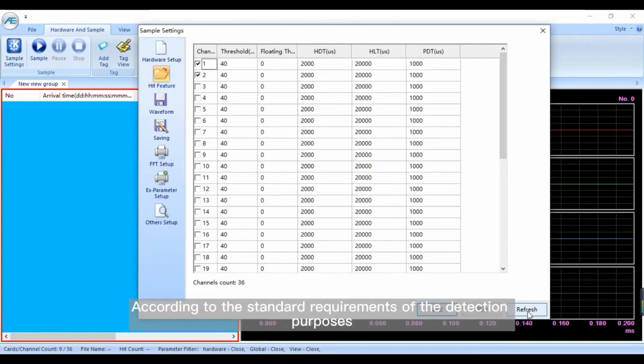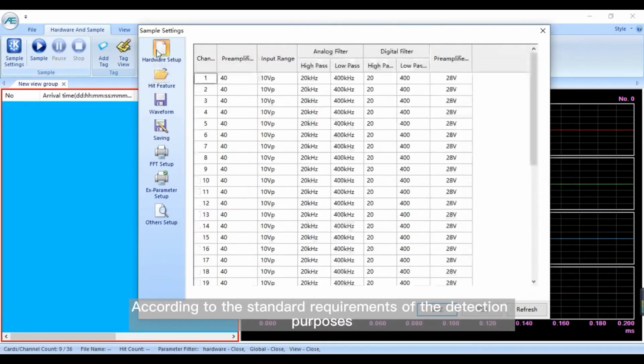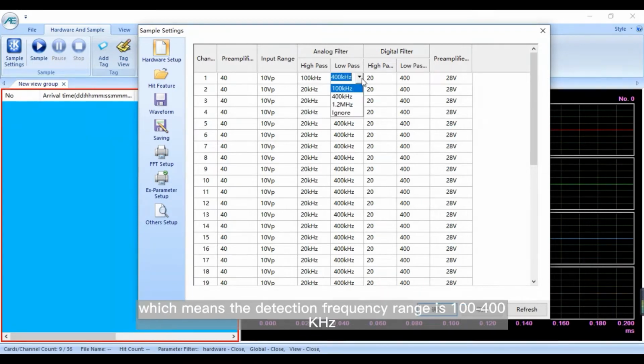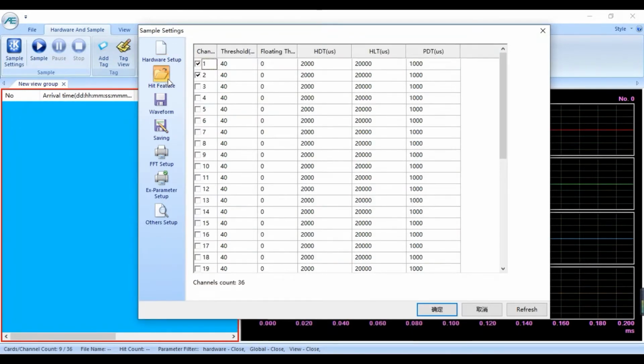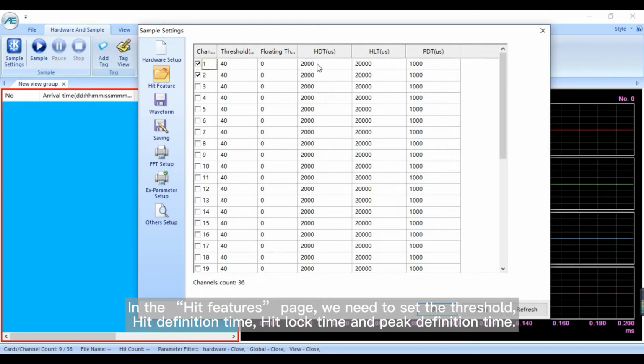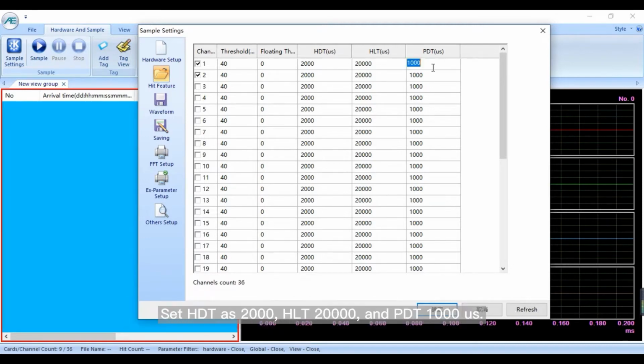According to the standard requirements of the detection purposes, the filter is set as 100 kHz high pass and 400 kHz low pass, which means the detection frequency range is 100 to 400 kHz. In the Hit Feature page, we need to set the threshold, hit definition time, hit lock time, and peak definition time. Set HDT as 2000, HLT 20,000, and PDT 1000 microseconds.